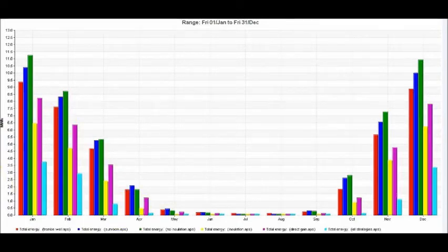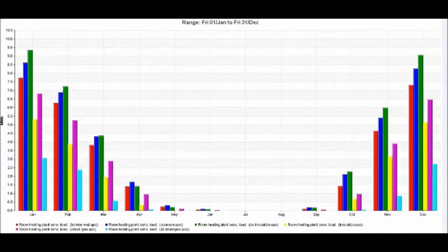And eventually, the cyan-colored bars show that when all of the strategies were put together and tested together, there was a drop from 49 megawatt hours to 12.8 megawatt hours, which means there is a 74% reduction. The results for the amount of room heating loads are quite similar to the total energy.